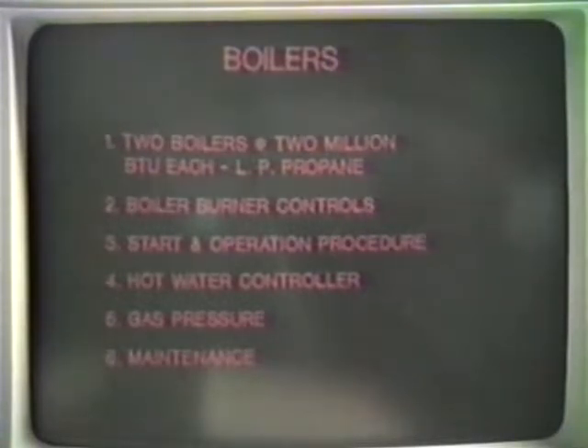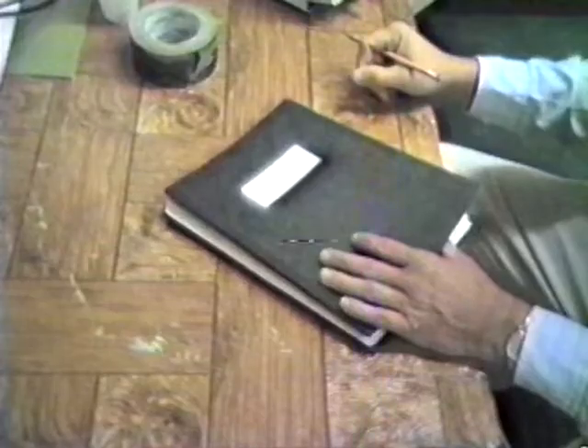Upon demand to fire, the blower starts and purges the boiler burner section for approximately 1.5 minutes. The burner then is ignited by the electric pilot. Low fire operation occurs for approximately 30 seconds to 1 minute, and then high fire burning comes on. Each boiler has its own temperature controller that sets the fixed water temperature that the boiler tries to maintain. These are adjustable. Also, each boiler has a gas manifold pressure indicator that's visible. We'll look at that when we go to each boiler.